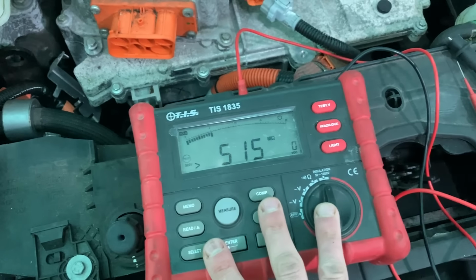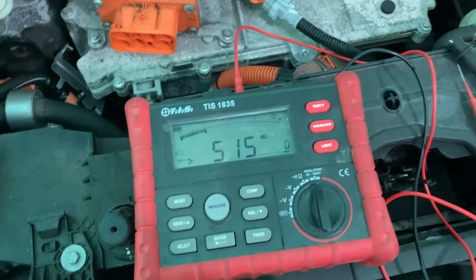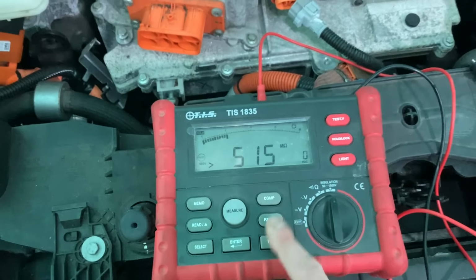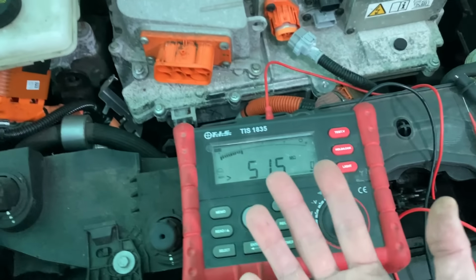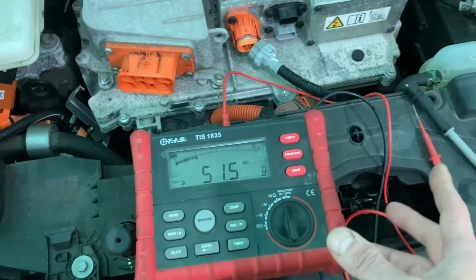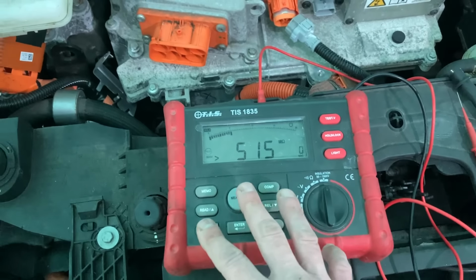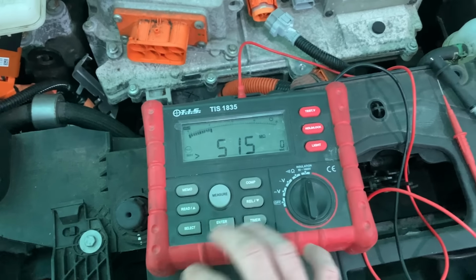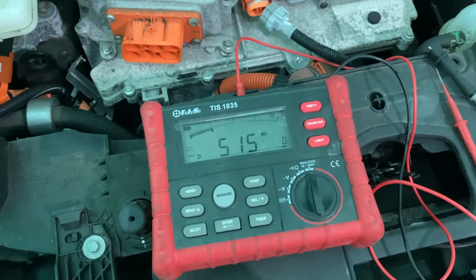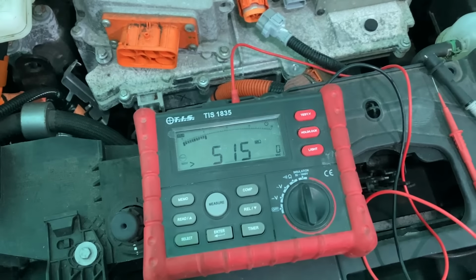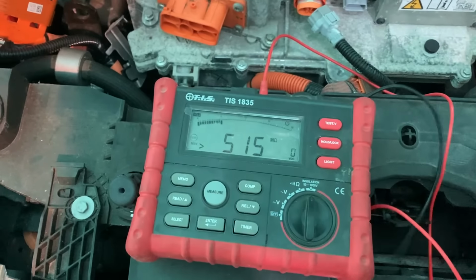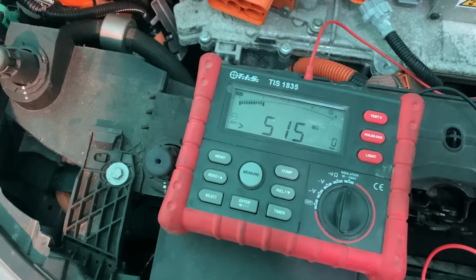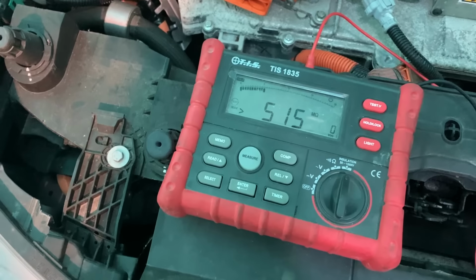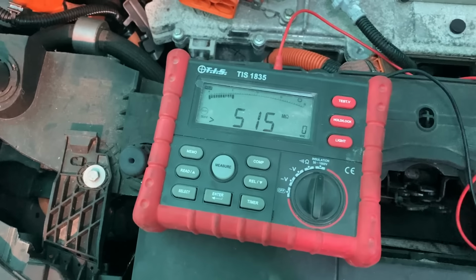But as I say, this meter has proven to be very reliable. Although it generates 500 volts, at this point I'm not using my gloves because the car's been locked out. You might think, that's a dangerous voltage - but this meter is run by AA batteries. It generates literally just milliamps. We don't need a lot of current to work out where this voltage is leaking - we just need a high voltage, to get that current, that voltage, to jump effectively.